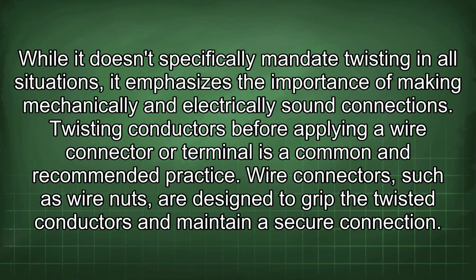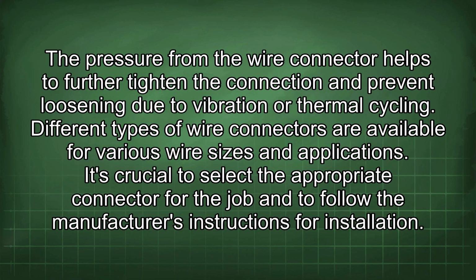Wire connectors, such as wire nuts, are designed to grip the twisted conductors and maintain a secure connection. The pressure from the wire connector helps to further tighten the connection and prevent loosening due to vibration or thermal cycling. Different types of wire connectors are available for various wire sizes and applications.